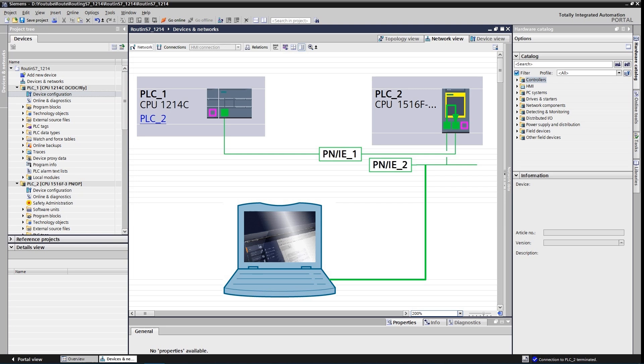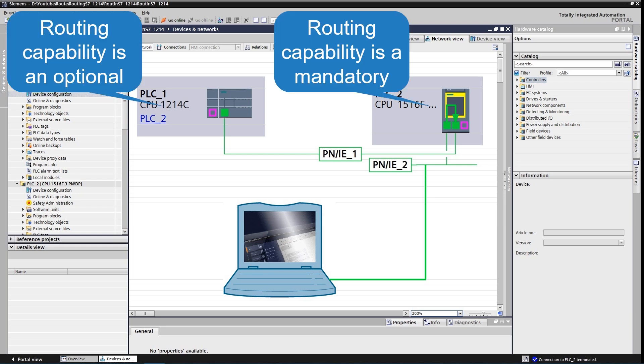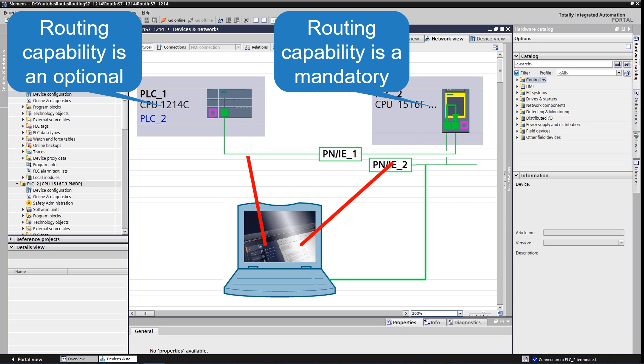To be able to use S7 routing, all but the last one device must support S7 routing. All the devices must be configured in Step 7. As CPUs play the role of an S7 router, the routing information is obtained by downloading hardware configuration to the CPUs.